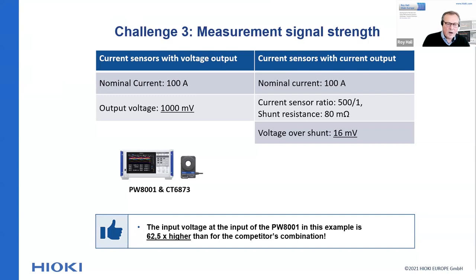If we look at one of our known competitors, the situation is as follows. The 200 amp sensor will generate an output current of just 200 milliamps when it's measuring an input current of 100 amp. The current output is then connected to an internal shunt that has a resistance of just 80 milliohm. The generated voltage at the input of the power analyzer, in this case, will only be 16 millivolt. If we compare that with the 1000 millivolt or 1 volt that the Hioki solution is providing, it becomes clear that the signal at the input of the PW8001 is 62.5 times higher than at the input of the other power analyzer. You can imagine this has a huge impact on the signal to noise ratio for your current measurement.